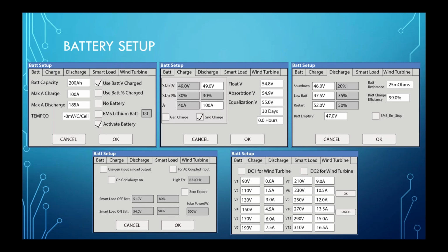And then you move on into the charge discharge tab. Here you will be able to change the float, absorption, and equalization. If we do not have any communications where the BMS is giving us all this information, we do recommend changing these to reflect the batteries you're using. It's very important. Lead acid batteries are a lot higher in terms of voltage than typical lithium batteries, depending on the manufacturer. But this is very important just to prevent any damage.